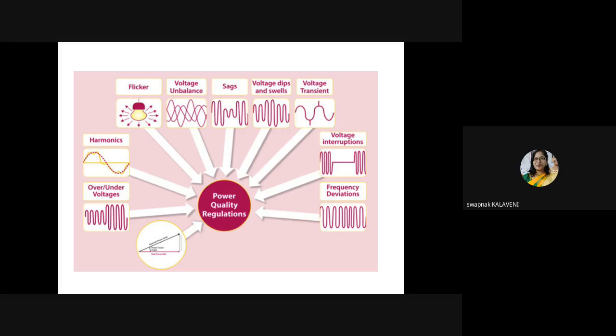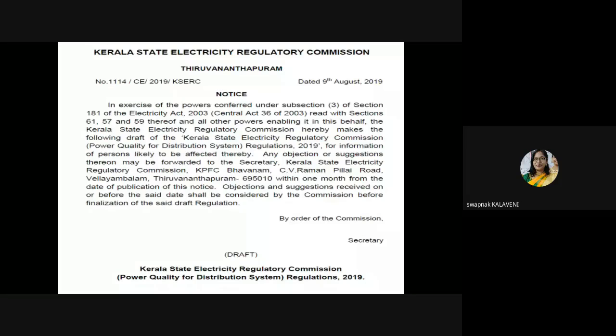Say, for example, what are the power quality issues? Frequency deviation, voltage interruption, voltage transient, voltage dips and swells, voltage sags, voltage unbalance, flickers, harmonics, over or under voltage. These are the common power quality problems in the system, for which the Forum of Regulators has introduced a lot of regulation, a lot of recommendations. We will discuss them one by one.